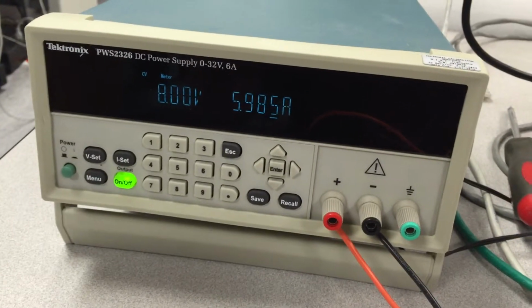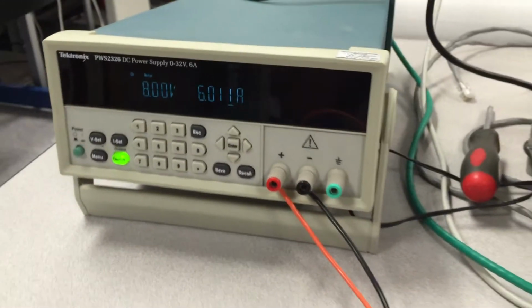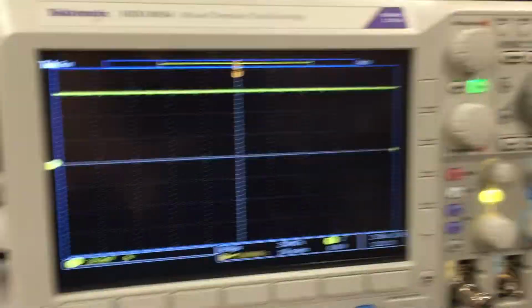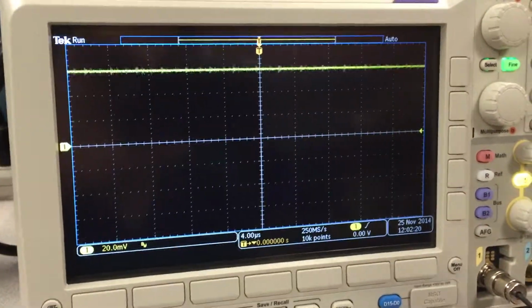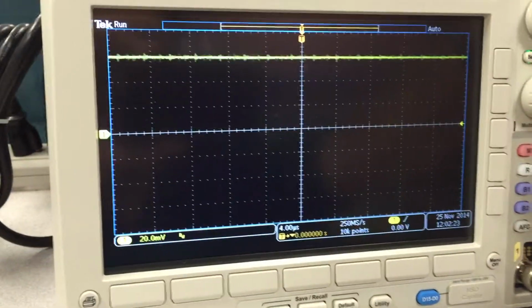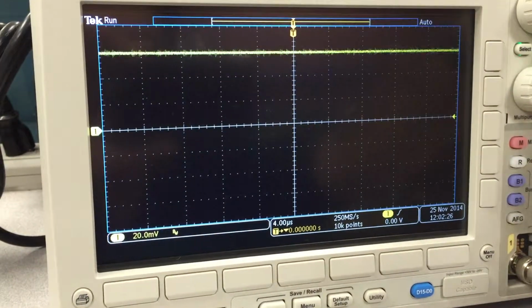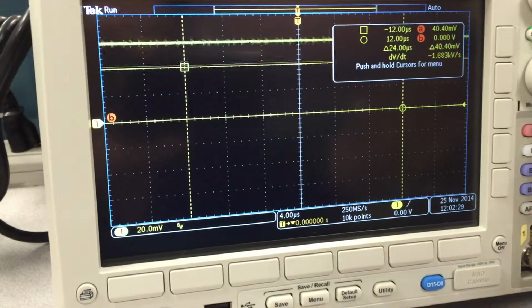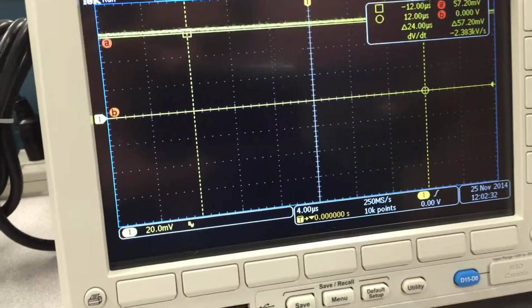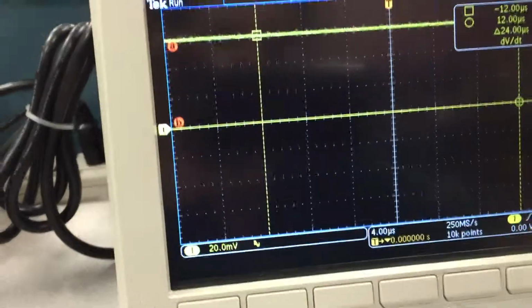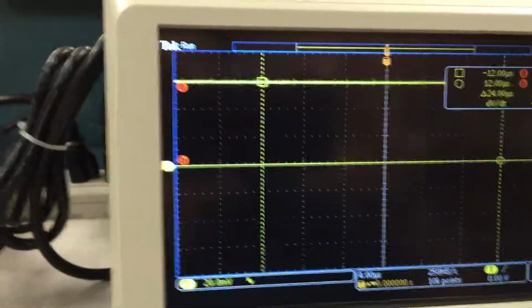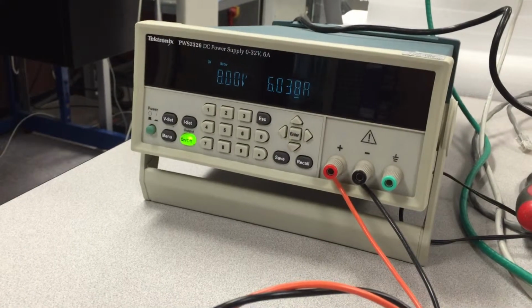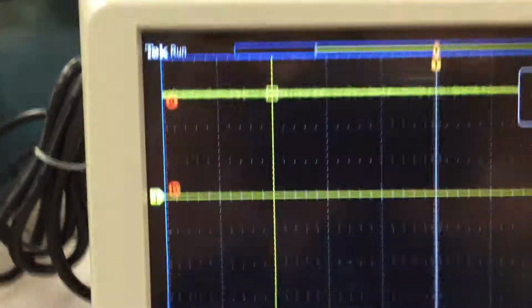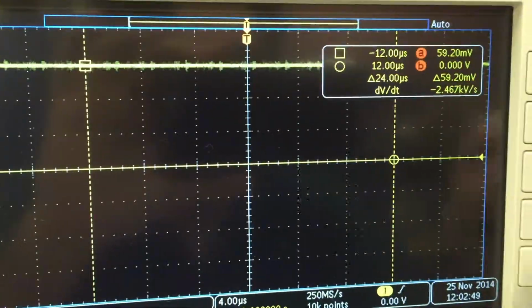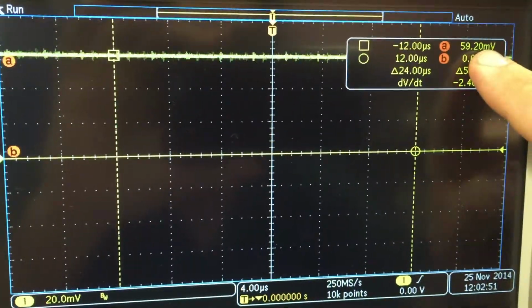Let's see if we can get that a little better. Okay. And here we see our measurement on the scope. And this is in the DC domain, of course. This current sensor is good up to the range that we're using it for these power supplies, which is around just over 100 kilohertz. So we're going to make a quick measurement of our voltage here.